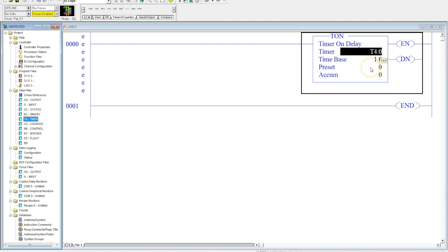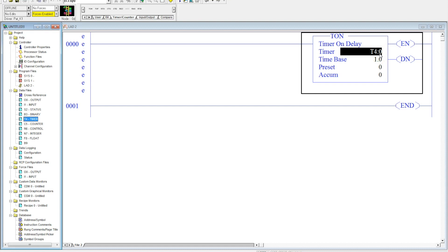It's located in the T4 data table file, and this would be timer zero. You can have up to 256 timers in this program in this one data table file. So you would see T4:1, 2, 3, 10, 12, whatever the number is that the programmers used before. Most people just start off with zero and work their way down through it.